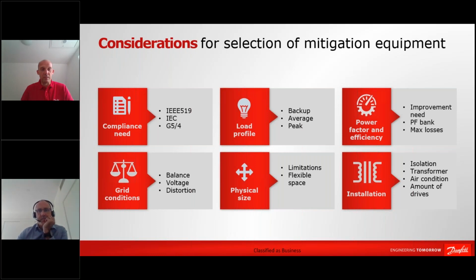What you should be doing is actually look at the source of the second order. So can you change the loading? Can you move some of the single phase loading from one phase to another phase so that you have distributed your single phase loading more evenly? That would be my advice. Or you could consider adding filtration in front of the single phase loading, simply to get a better balance on your power supply.